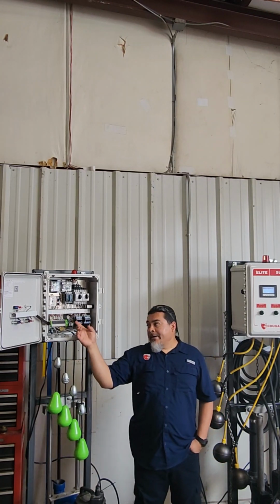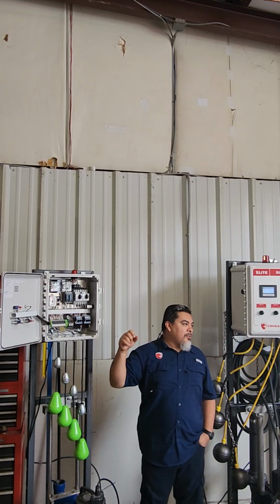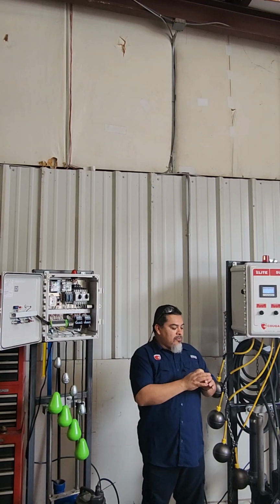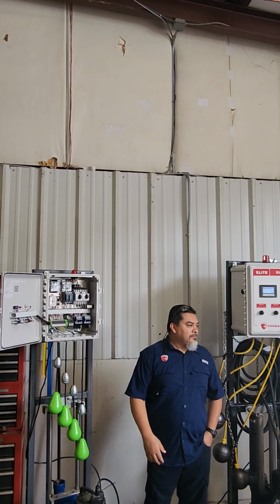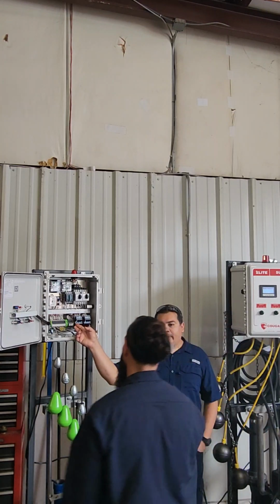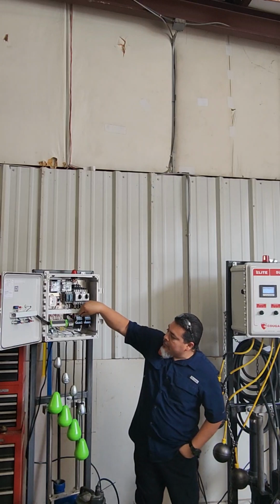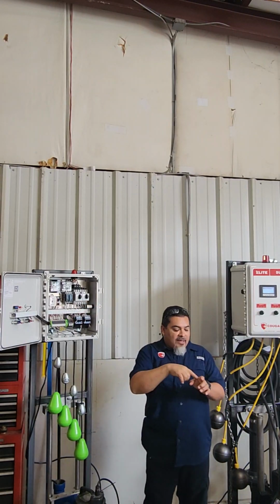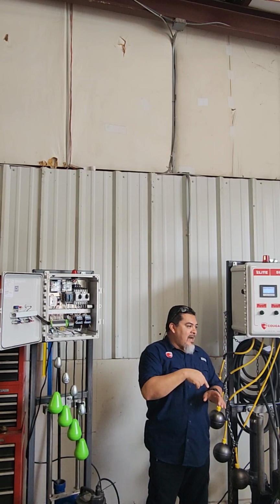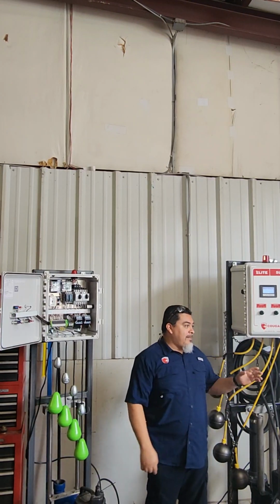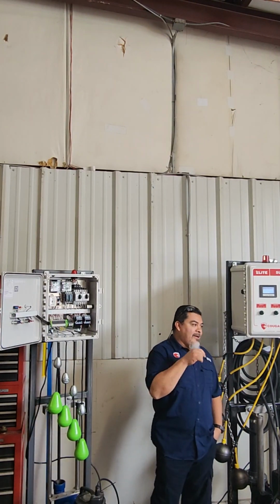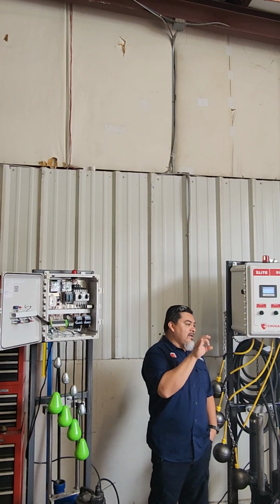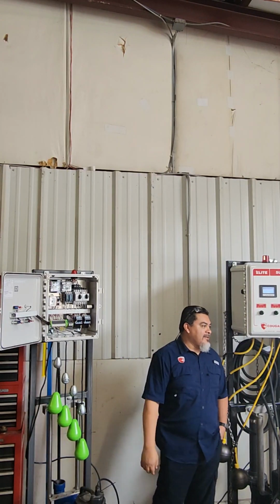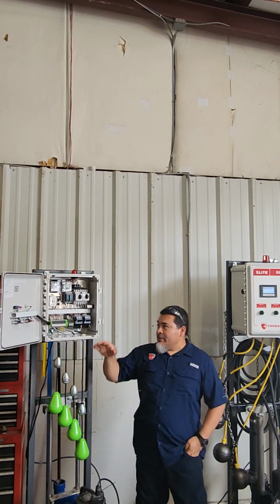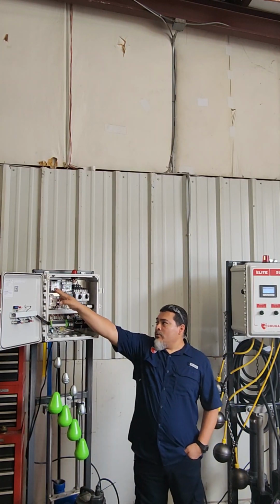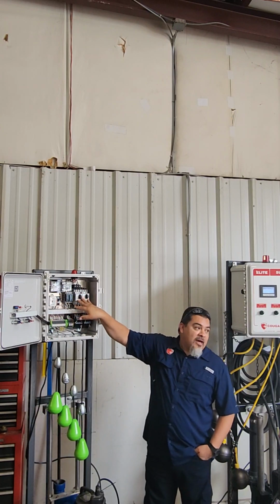Another thing will be your contactor coil. After so many usages, it will swell up. Where's that at? Internal of the contactor. It's internal? Okay. But for example, this one has this on top, but some have a little thing you can push in to activate the pump. Some people use a screwdriver to bypass everything, which is not something I recommend. But if you press it when the power's off and it's locked up, the whole contactor is replaced.